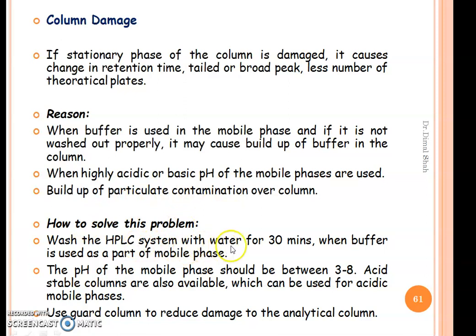Wash the HPLC system with water for 30 minutes when buffer is used as a part of the mobile phase. So once your analysis is over, to remove buffer out of the column and out of your instrument, at least wash your column with HPLC water for 30 minutes. Warm water can be preferred.